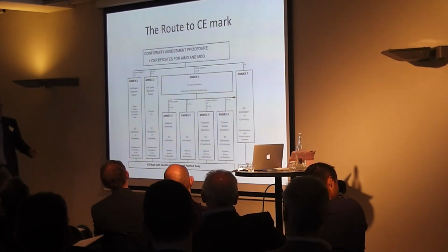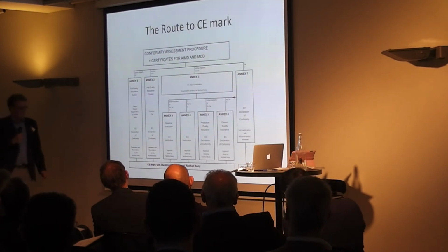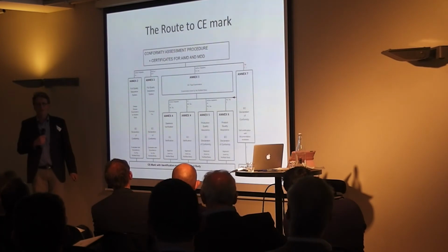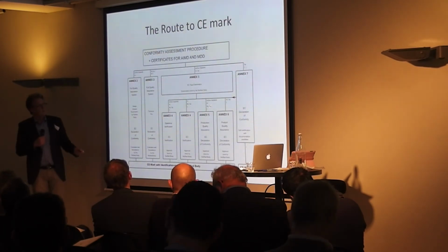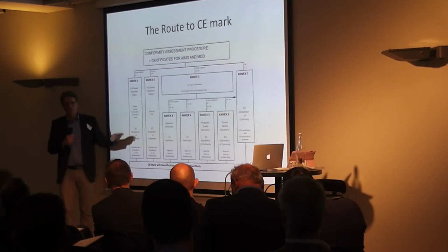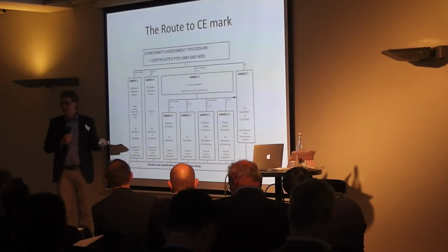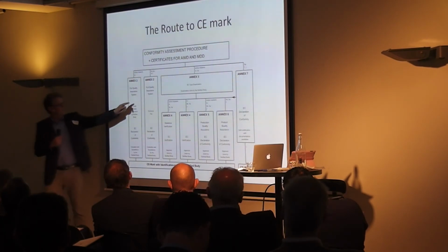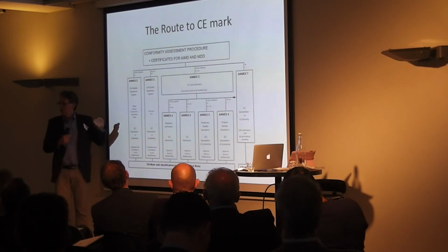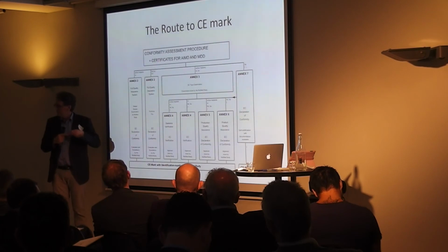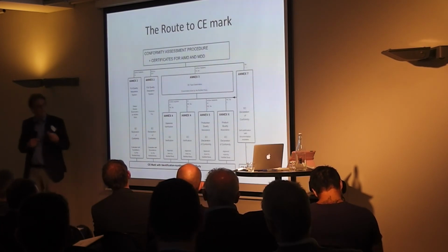Then you need to establish a quality system and have your notified body check if you comply with it. There are different other ways, other categories, but for software, I really wonder if these categories would apply. So basically, this is full software development and quality system development. You need to develop software in a systematic manner. And that's why you have to have a set of SOPs, how you develop your software, and how to deal with continuous integration of the software, design changes, integration of them.